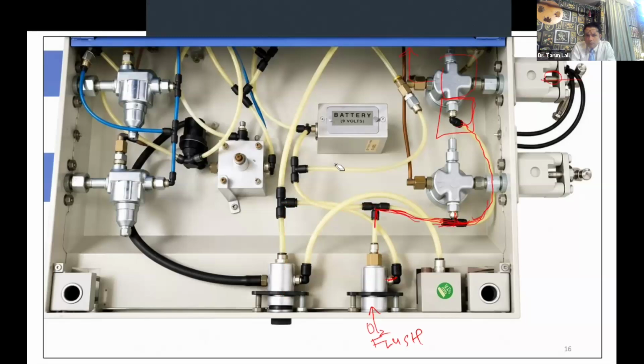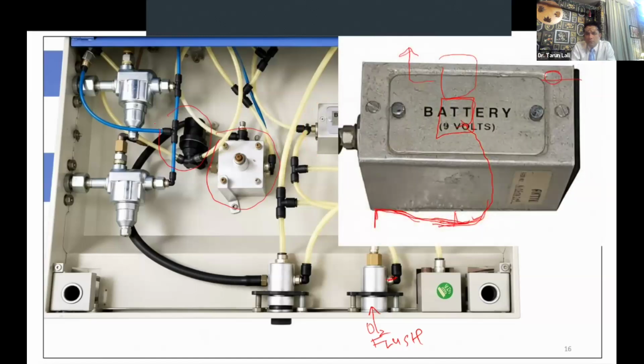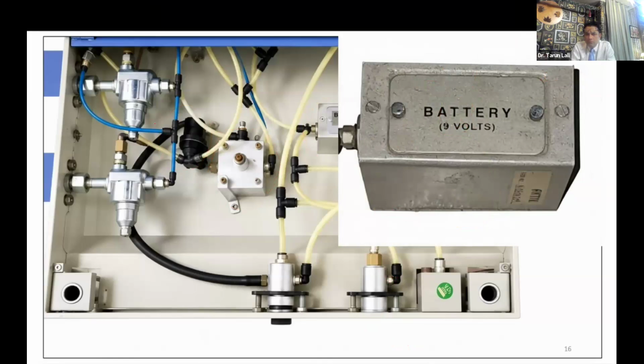So now let us trace the oxygen further beyond the oxygen flush. Just as we see, there are three things that attract attention. One is this large aluminum thing, which has battery written. The other is probably this large thing. And the third is this black plastic thing. So let us just see what they are. The first thing that you see where battery is written is your hypoxia alarm. It is that inaccessible, unmutable hypoxia alarm, which is exposed to 40 to 60 psi of gas pressure. And the moment the gas pressure falls below 40 psi, this oxygen alarm is triggered, and then the anesthetist cannot mute it because it is hidden under the tray. And you see there is no mute button on it. That is the first thing.